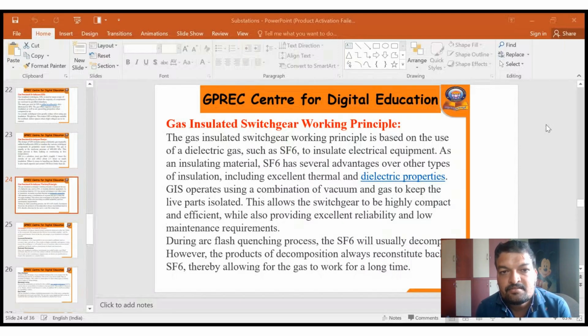So, coming to the gas insulated switchgear working principle. SF6 gas has better dielectric properties as compared to air, and it has better insulation and quenching properties as compared to air. The working principle of a gas insulated substation is based on the use of a dielectric gas such as SF6 to insulate electrical equipment. As an insulating material, SF6 has several advantages over other types of insulation, including excellent thermal and dielectric properties.